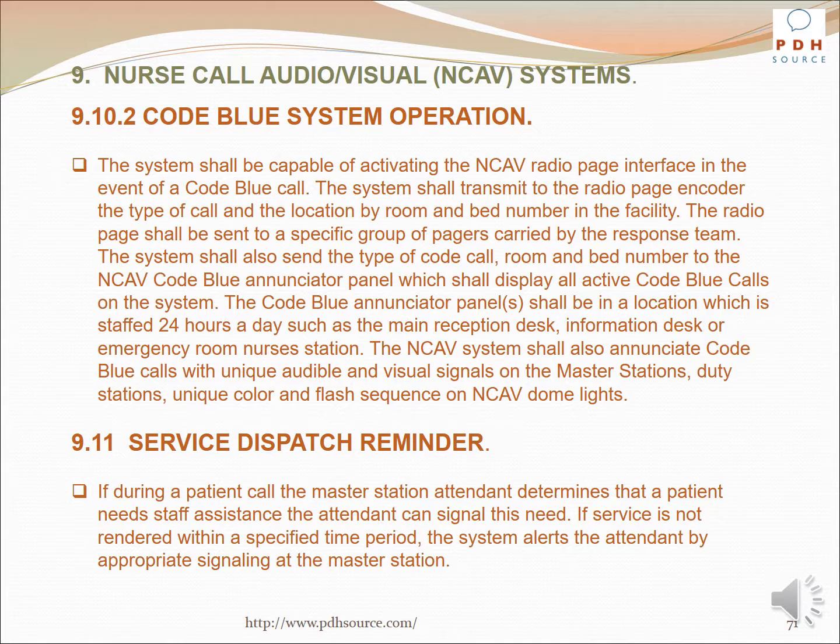If during a patient call the master station attendant determines that a patient needs staff assistance, the attendant can signal this need. If service is not rendered within a specific time period, the system alerts the attendant by appropriate signaling at the master station.